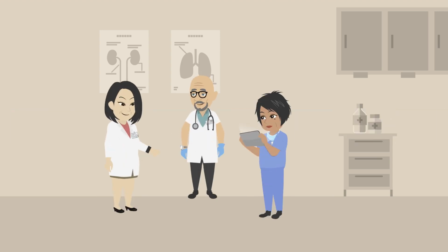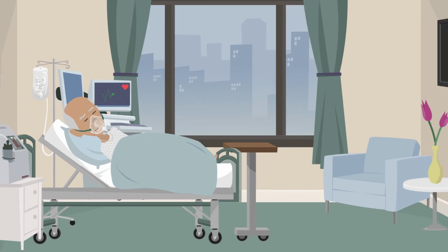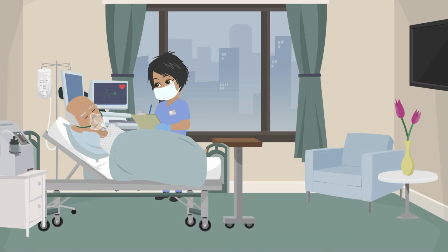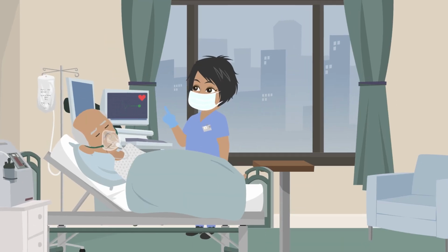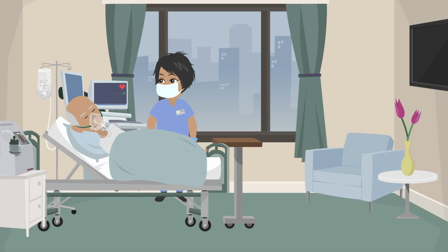Getting started with alarm management begins with having a good team in place and having correct data. There are so many alarms, and they are so often false or not actionable, that nurses and other clinicians are beginning to become desensitized to, or ignore, alarms. They turn them off. That has led to missed true patient events. So it's a patient safety issue that we are trying to address.